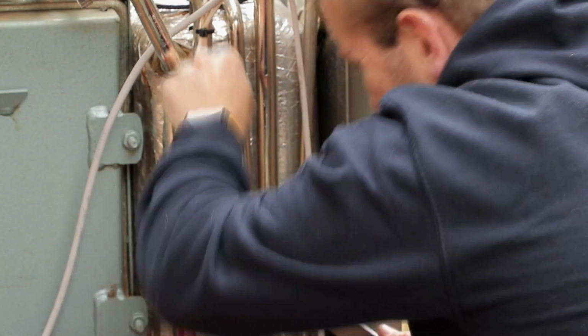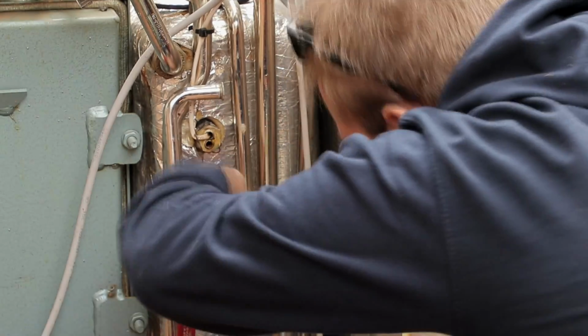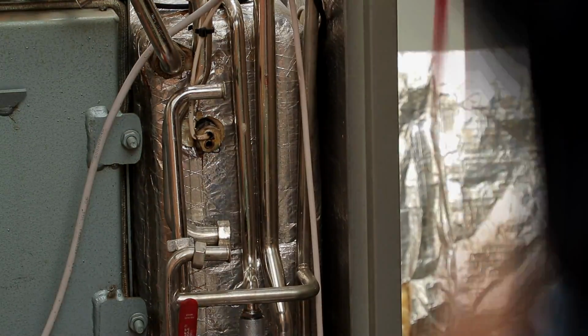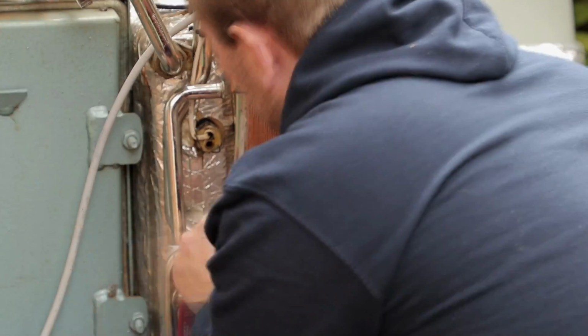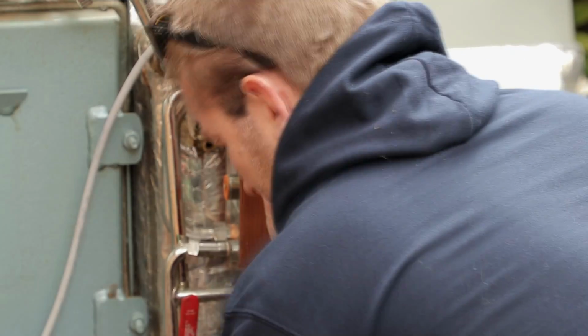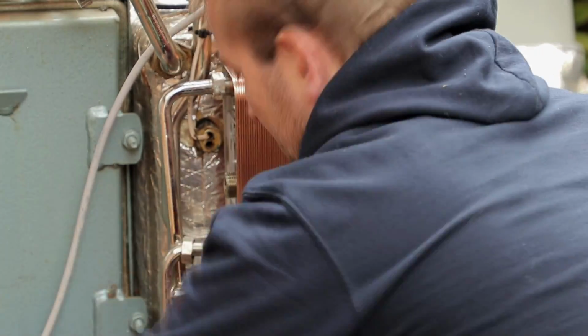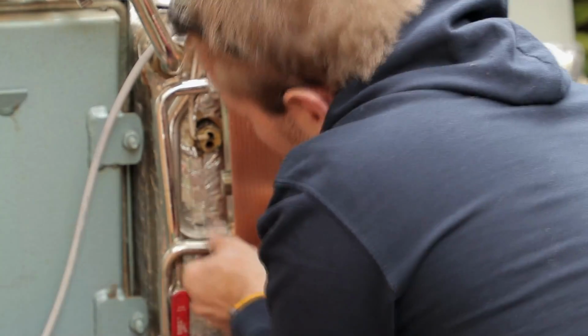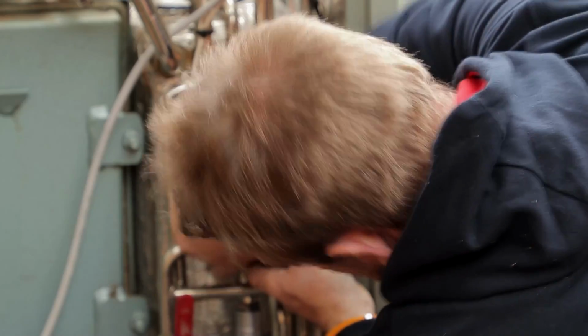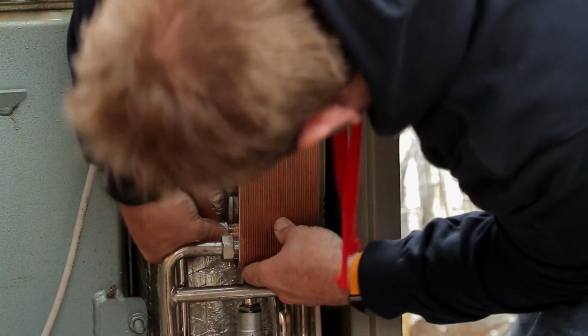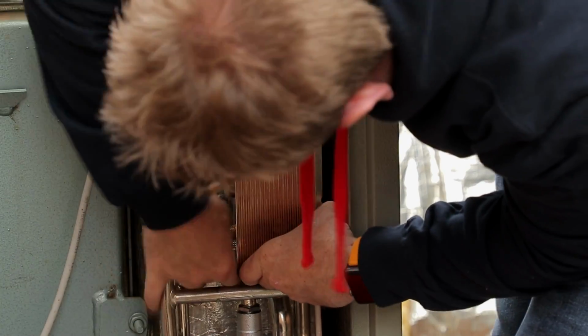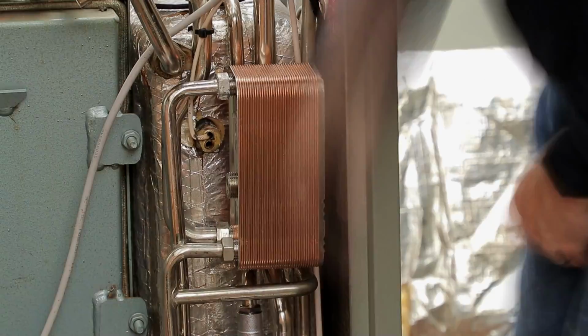Once we've done that, I'll then drop the pressure out of the heating system using either a drain off valve or, quite naughtily, a high pressure relief valve. Oh dear. After this, I'll grab some towels and some diversionary buckets to channel the water away from any electrical components, because there does tend to be a lot of electrical components inside these boilers. Then it's a matter of whipping the nuts off, taking out the old heat exchanger, getting the new one in with our lovely pre-jointing compounded fibre washers, tightening them up, and then reinstating the system.